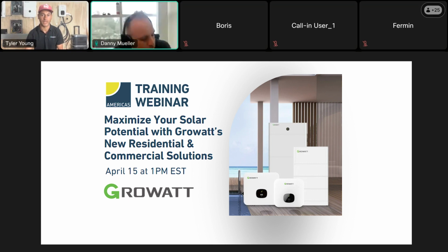Yeah, it's good at partial home backup, and it's definitely value driven. If you want the whole home residential backup, go with the MIN system, tried and true. But the SPH is a lot more flexible depending on what you're getting at. But yeah, mainly for partial home and then off-grid applications, things like that. But it sounds like it's not quite service entrance rated. Correct.